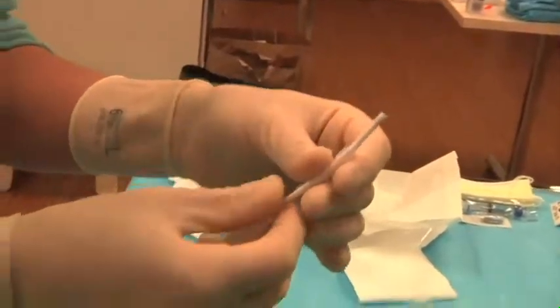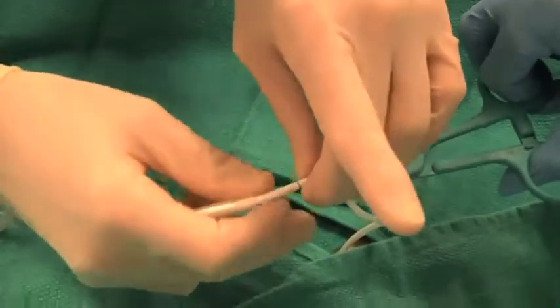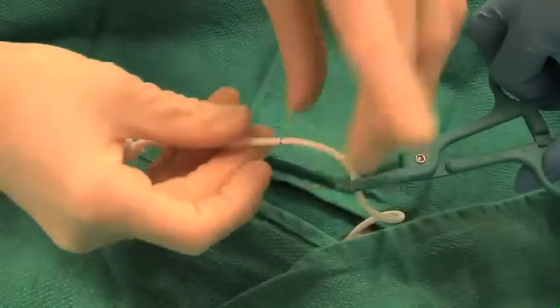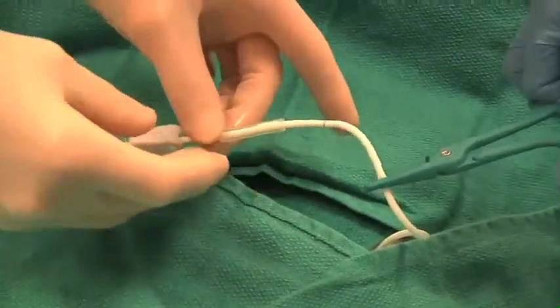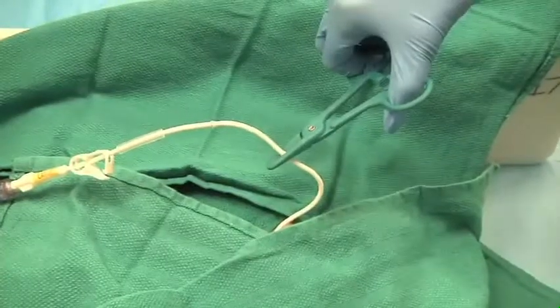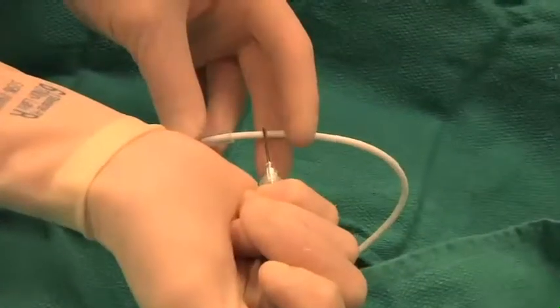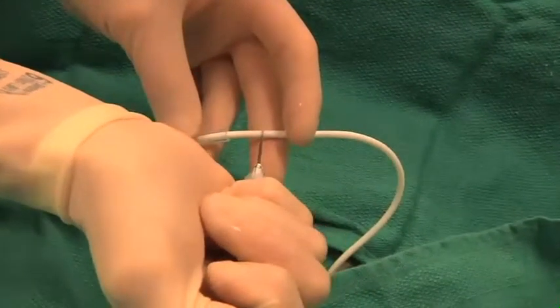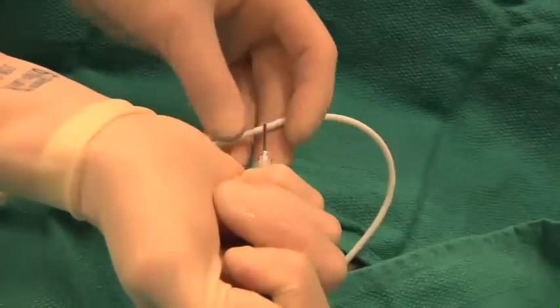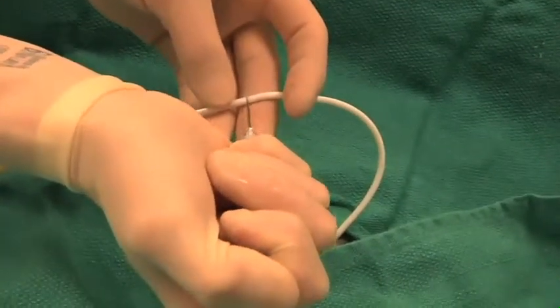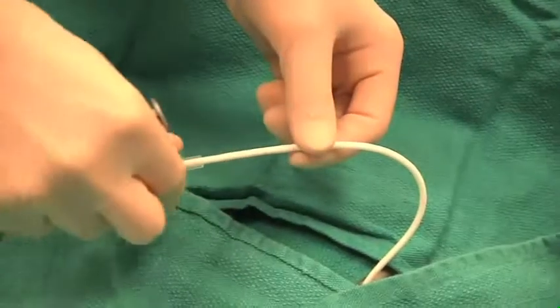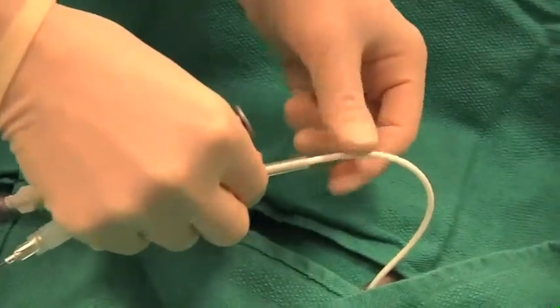Loosen the sleeve. If you're repairing a multi-lumen catheter, match the stem side size with the lumen size. One is larger than the other. Remove the clamp. Inject glue into the opening between the joints of the catheter and the repair kit. Push the catheter and the repair piece together.